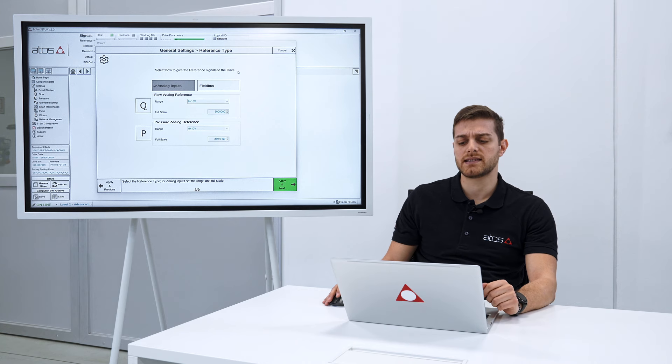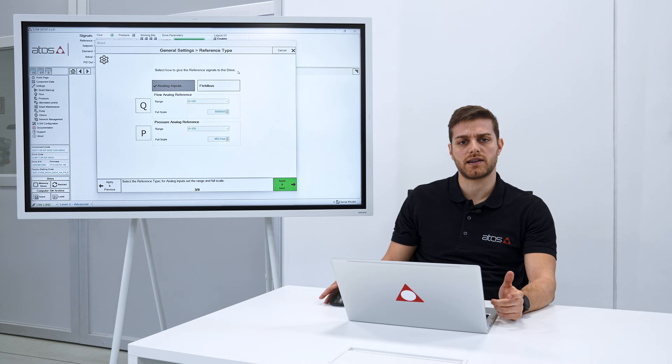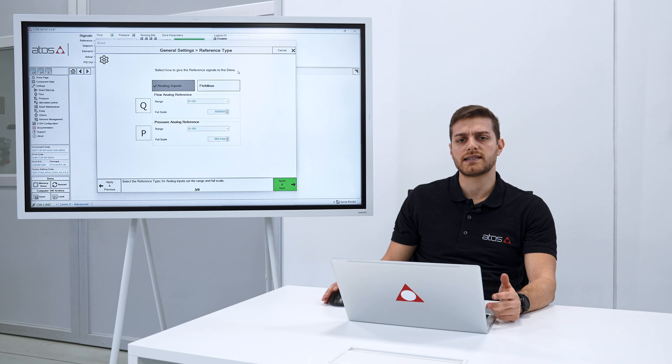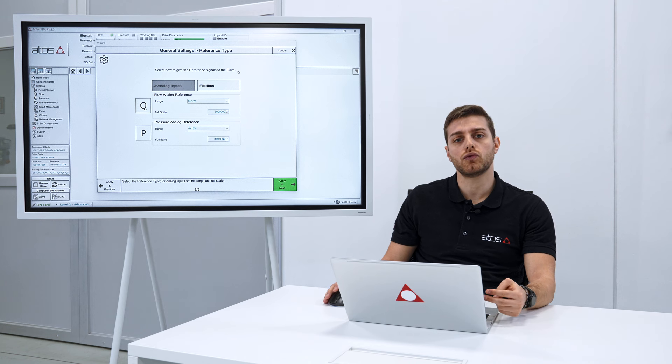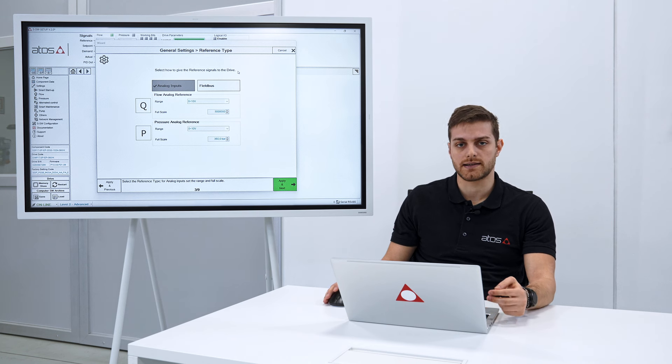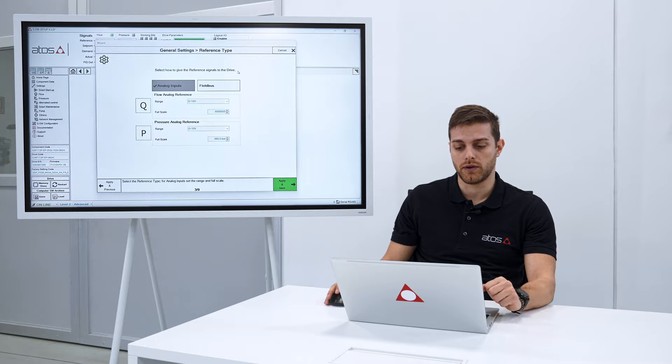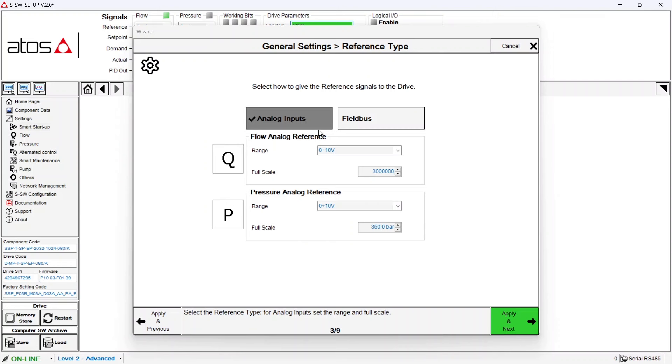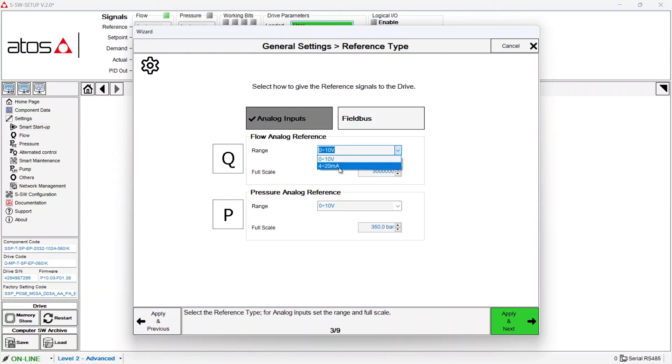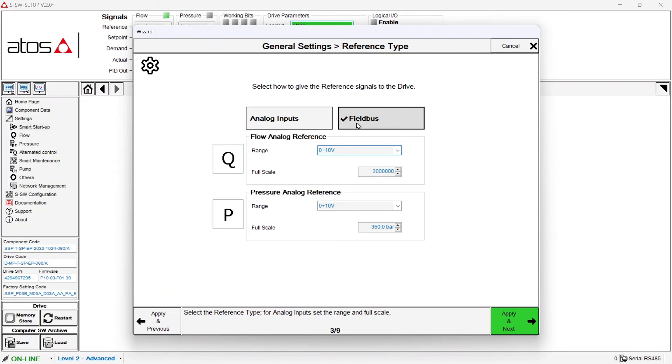The third step is asking instead for the reference signal. The servo pump will require to have two reference signals, one on pressure and one on flow rate. In this case it's asking us how to give it, through analog or through field bus. Through analog you can decide to give it through voltages or through current. In this case we are again selecting field bus and we can go on.